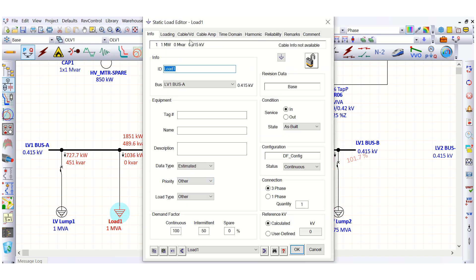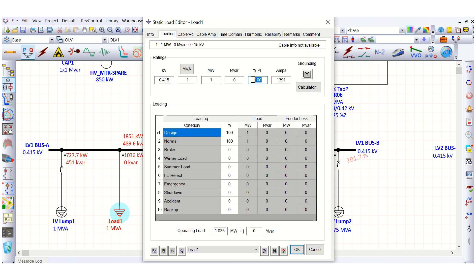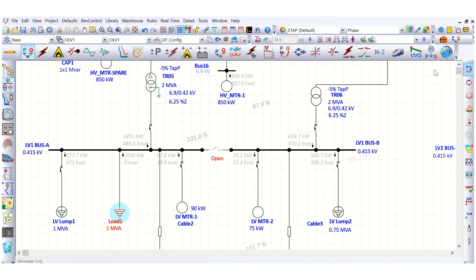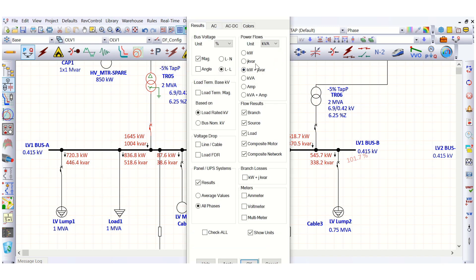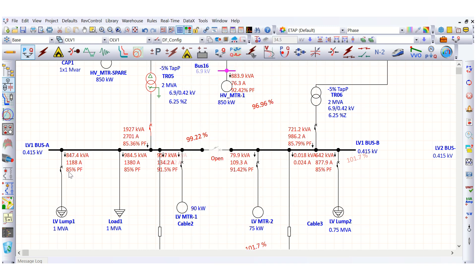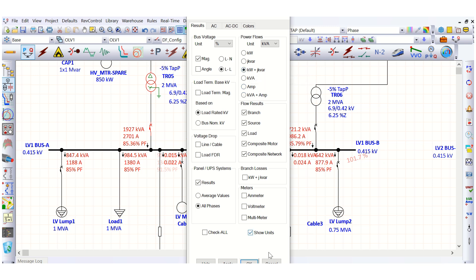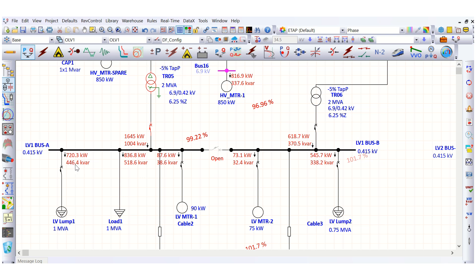Now let's change the static load power factor from 100% to 85%, matching the lump load. We'll run the load flow again. You can see that even though the power factor is 85% for both the lump load and the static load, the real and reactive power drawn by these two loads are still different. The reactive power drawn by the lump load is 446 kVAR, while the static load draws 518 kVAR. Why this difference, though the power factor is the same for both cases?